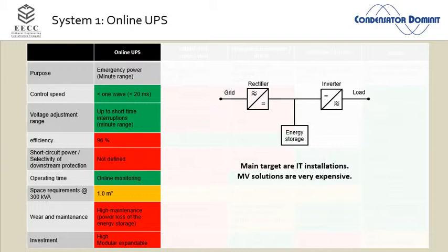And the more short circuit power I have, the better it is. I have two advantages. The one is selectivity. My fuses, my circuit breakers, they trip exactly as they are planned to trip. A fuse will blow if the current is high enough.